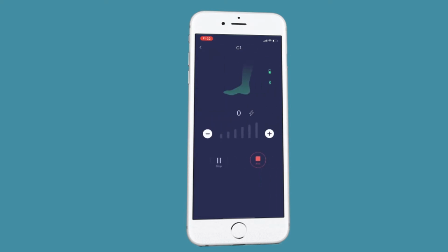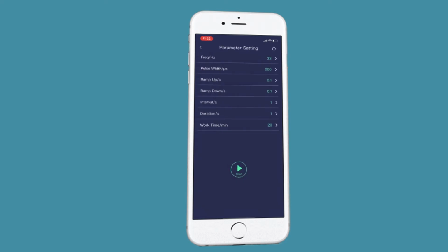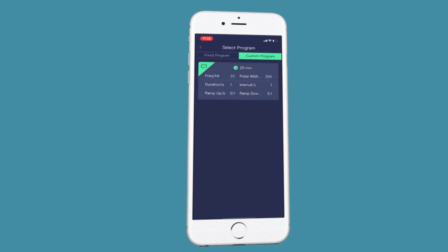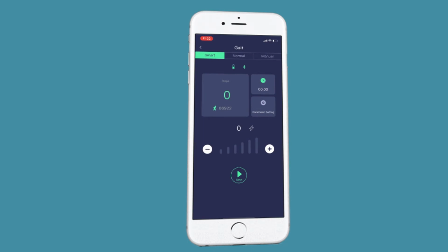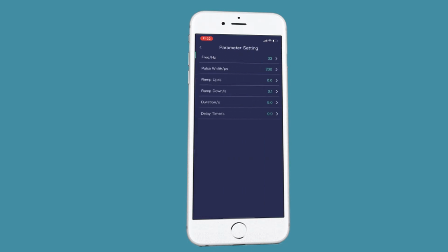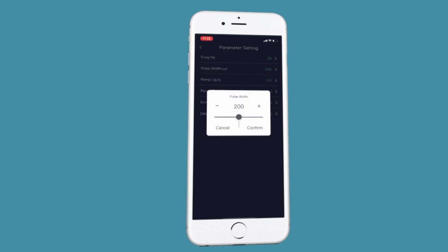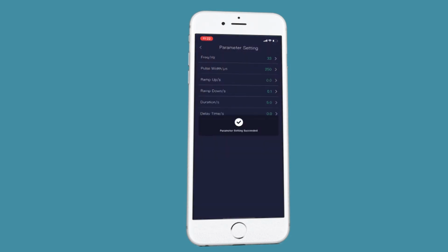And you simply customize a program if that's what you wish. You hit start, increase the intensity to an appropriate motor response, and go through the exercise program. When you hit end, on all the modes, you have to press it and hold it for around 3 seconds. That's a safety feature to make sure it's turned off properly. And then in gait mode, we have 3 modes. We have smart mode, normal mode, and manual mode. And there are some default parameters that can be easily changed in all of the modes. I'll quickly change the pulse width mode to show you that, and it's sent.